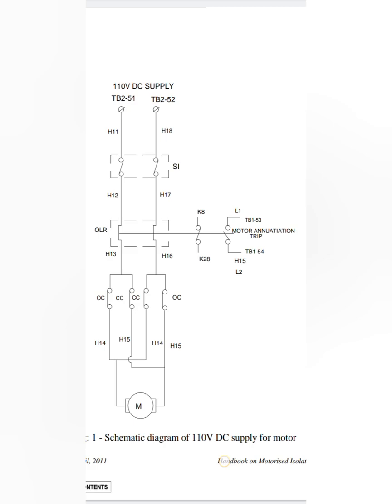The main thing is that in here we are using DC supply as we are using DC motors. In most of the cases we will use AC motors and AC supply. In here we have a switch for controlling S1, then OLR which means your overload relay. Normally this OLR will be connected in series with your motor supply. Whenever the OLR gets tripped or operated due to some malfunctions or thermal overload, automatically our supply will get cut off, and from that OLR one alarm will be initiated — a motor trip or motor trip initiation alarm will go from your OLR relay.